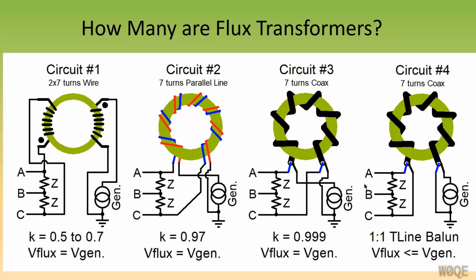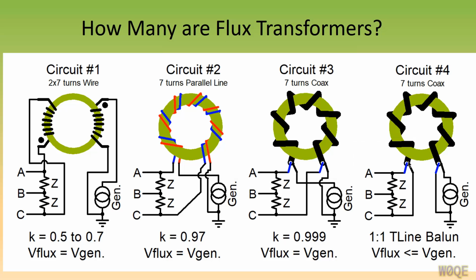In this circuit right here, if I connect point C to ground, there is no flux in this transformer to speak of. If I connect point A to ground, we see a voltage - connecting A to ground, we see a voltage from here to here of the generator voltage. This sees a common mode voltage across the core of the generator voltage.